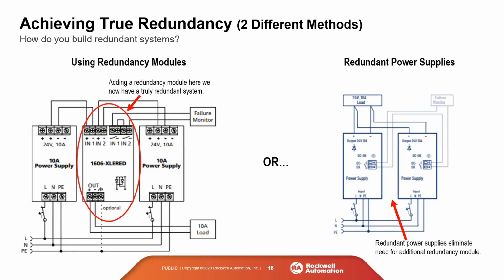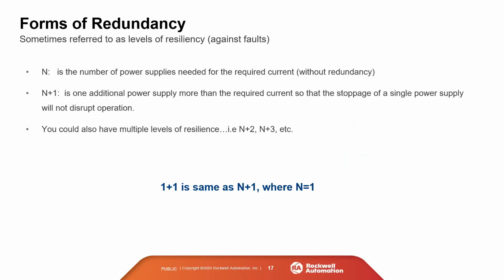But we also have another option on the right, which is redundant power supplies. So there are power supplies that have that capability built into them. So same system, 2 different methods of doing it, but it achieves the same thing. So forms of redundancy, we talked about the 1+1 or the N+1. Basically, all that means is N is the number of power supplies needed for the required current without redundancy. And then N+1 would be that additional power supply required to build in the redundancy. You could have multiple levels of resiliency, so you could have an N+2, an N+3, and so on.